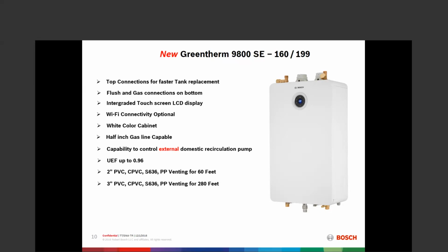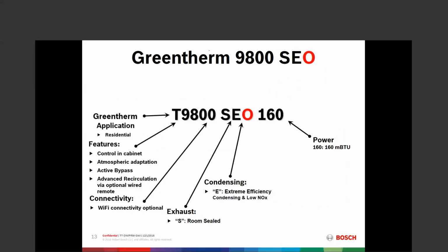If we cannot get the exhaust out in 60 feet equivalency, we can step it up to 3-inch, same materials, and then we can go up to 280 feet equivalency. Flexible polypropylene is also approved, which makes it very nice for some retrofit situations. So that's 2 units. Then we go to the Greentherm 9800 SEO.